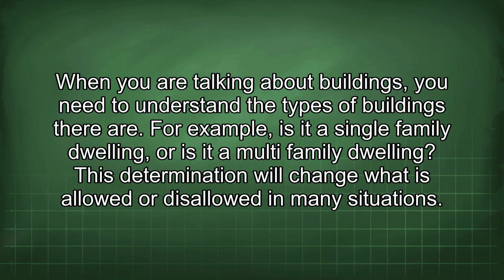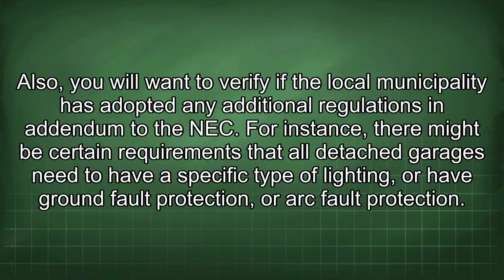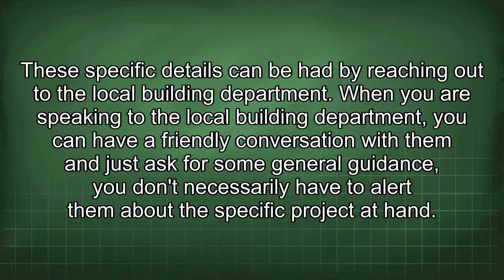When you are talking about buildings, you need to understand the types of buildings there are. For example, is it a single-family dwelling, or is it a multi-family dwelling? This determination will change what is allowed or disallowed in many situations. Also, you will want to verify if the local municipality has adopted any additional regulations in addendum to the NEC. For instance, there might be certain requirements that all detached garages need to have a specific type of lighting or have ground fault protection or arc fault protection. These specific details can be found by reaching out to the local building department.